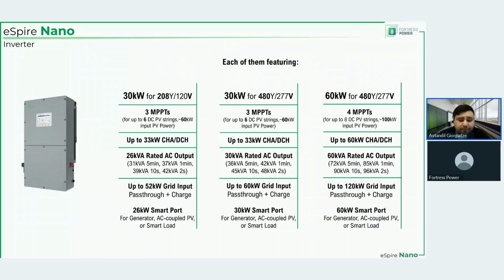And your understanding is correct. There is no 60 kilowatt 208 volt inverter. But because all of these inverters are scalable, you can have, for example, 208 volt 30 kilowatt inverters working in parallel, and that's going to deliver approximately 60 kilowatts of output power.